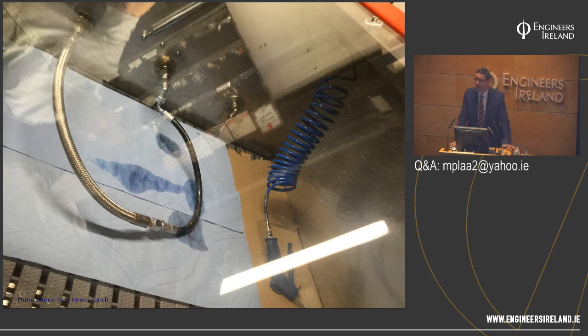And as a result, in the event of it going from standing pressure of 15, 20 bar up to over 100 bar, 75 flexible connections decided to come apart and left an insurer with a very large water damage claim. So what we did was, as part of our forensic investigation, we took a sample of the flexible connections to a specialist test lab, and we tested them under real world conditions. Can you see what happened when we ramped up the pressure? Leaked. Yeah? And that was down to them using non-listed, non-approved pneumatic hoses on a high pressure water mist system.